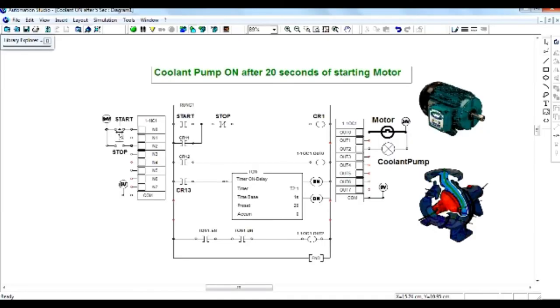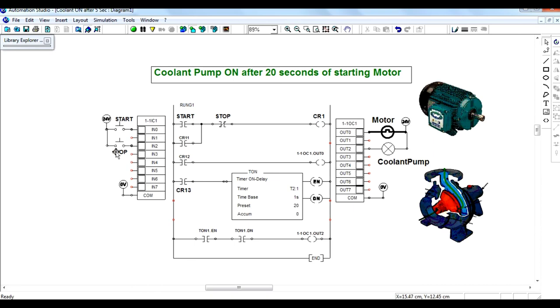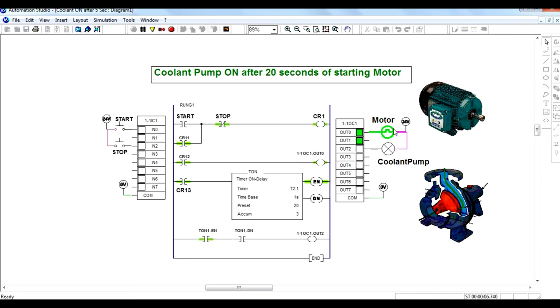The ON delay timer: here I have already built one ladder diagram for making a coolant pump turn on after 20 seconds of the motor starting. After the motor starts, the coolant pump turns on after 20 seconds. This is the start switch — let us make the motor on. The coolant pump is not on yet; it gets on after 20 seconds when the accumulation time is equal to or greater than the preset time.